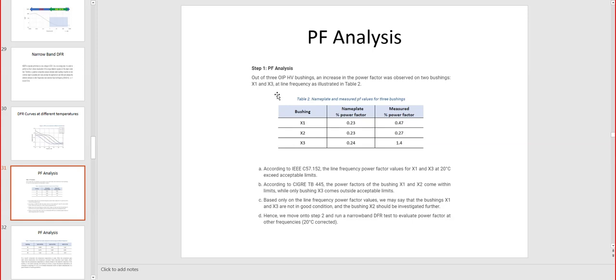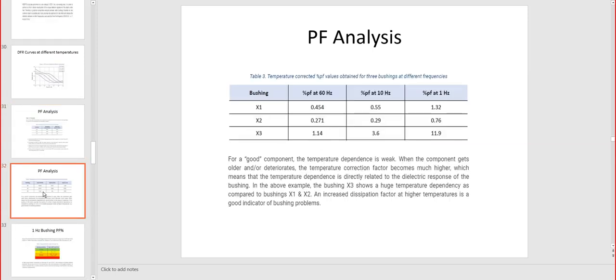Power factor analysis. So here is an actual reading from the main output transformer. We can see here the nameplate data and power factor in percentage. The nameplate data is actually 0.23 for phases 1 and 2 and 0.24 for phase 3. And the measured power factor was 0.47 on A, 0.27 on B, and 1.4 on C. So definitely they don't look good on phases A and C, especially on phase C. But we will see the root cause of this.